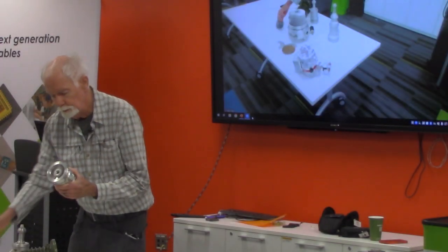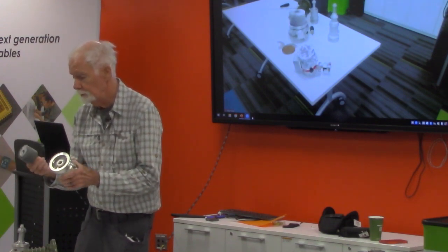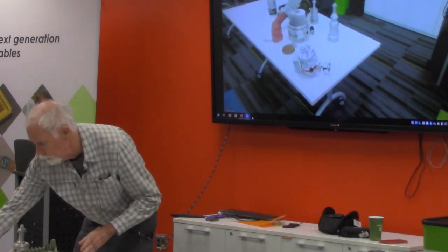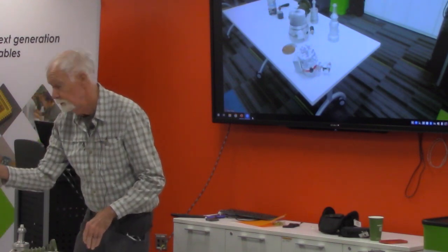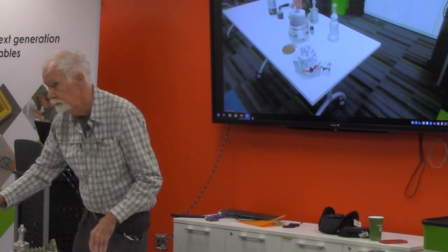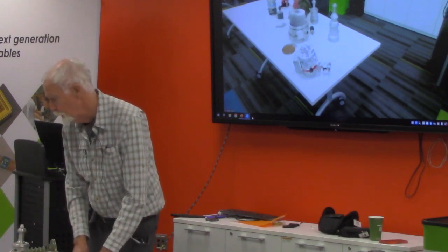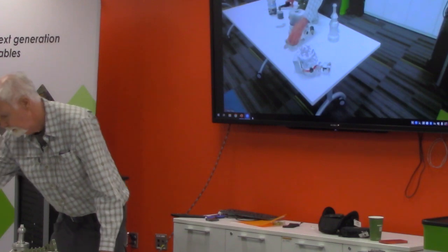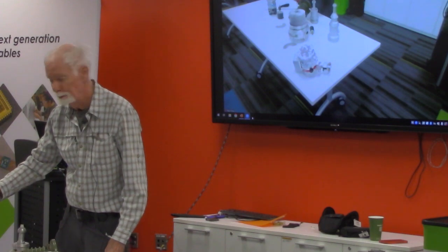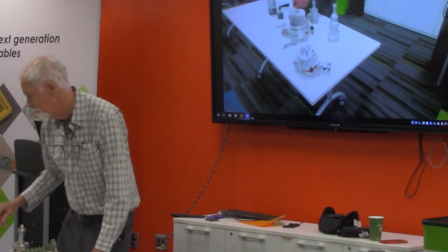Here's a small one. This was on a mass spectrometer. And this is exactly what goes inside of it. This doesn't have the stators in it. And the stators are going to look something like this. It's an aluminum base. These are high-tech materials. It's not just your normal aluminum. On the top of it, you'll have a splinter shield. So if you drop a screw in there, if something comes loose, it doesn't destroy it.